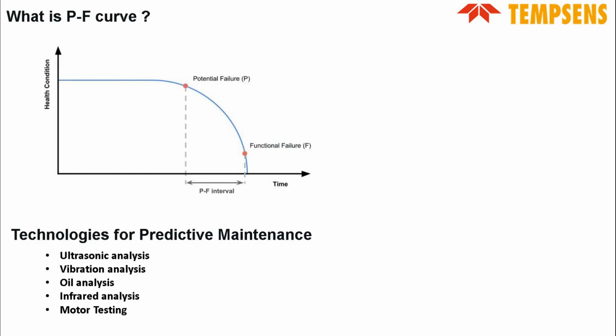What is a PF curve? The PF curve tells you the potential failure starting point and the functional failure point where the machine gets shut down. If you exactly understand or predict the failure, you can save the machine from functional failure by looking at this PF curve. There are various instruments in predictive maintenance which detect the potential failure of a machine, like thermal imager, ultrasound, vibration, and oil analysis. By using these techniques, you can identify the potential failure and stop it from going into complete functional failure.